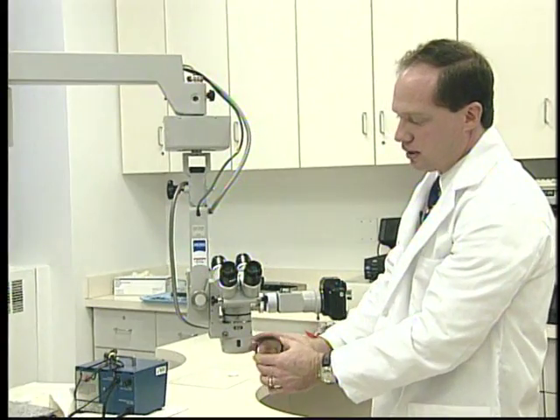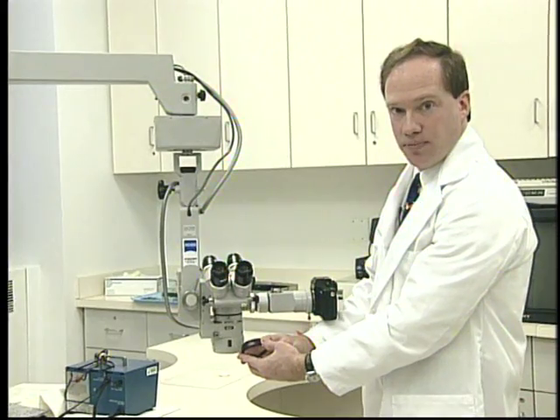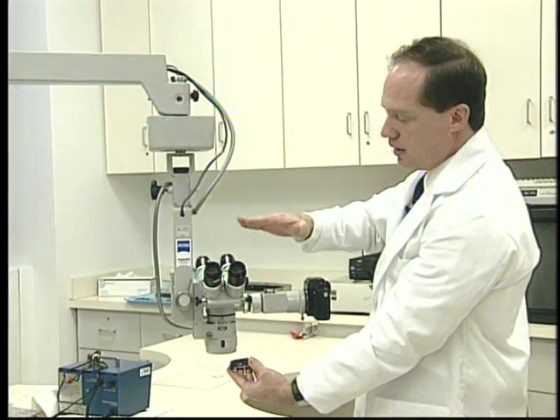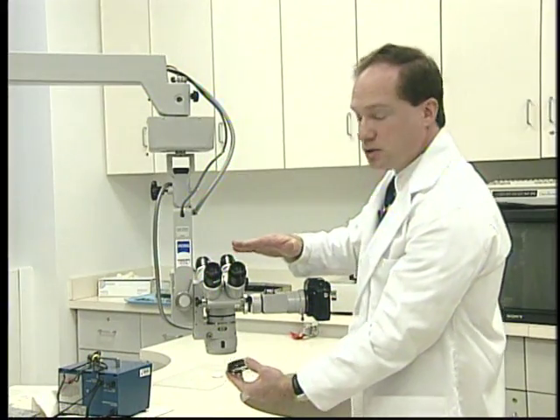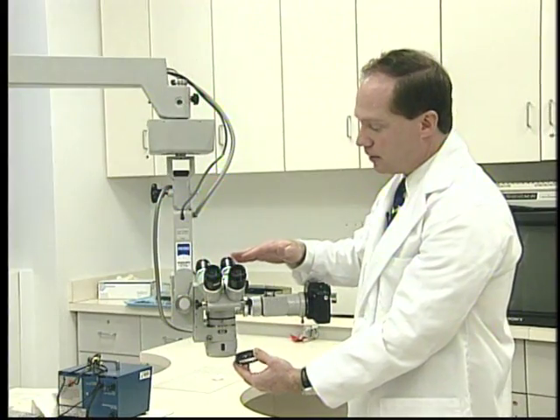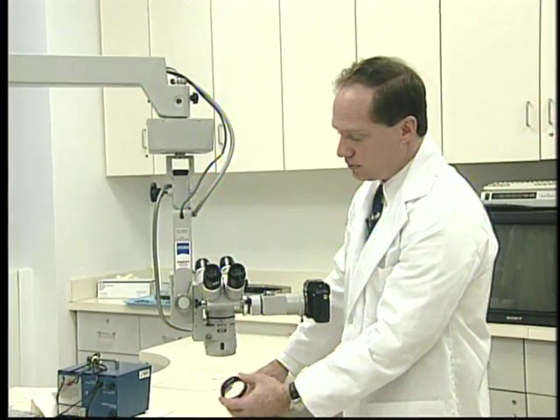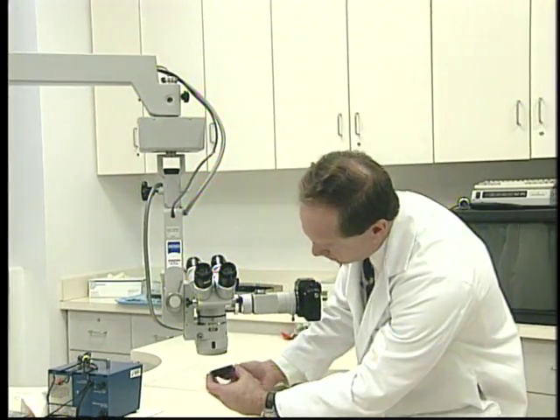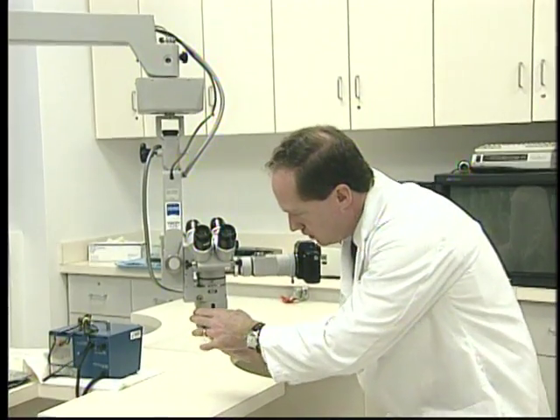We can show that this lens will focus at 200 millimeters. Now there are lenses with an f400 and various numbers, and what that means is that if you have an f400, your scope is going to be much further away, twice as far in fact, from the surface. This may be good if you're doing an ENT case, but if you're doing microsurgery on a limb, you want it to be closer so that your arms are not very far away from your working surface.